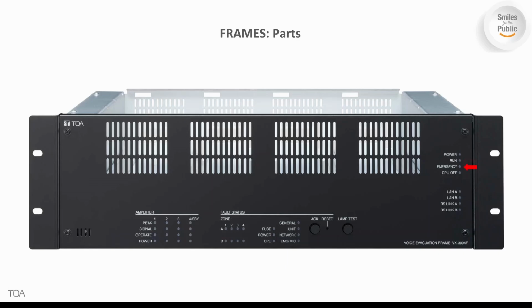The emergency indicator LED provides feedback on whether the system is in emergency mode. It lights red when it's in emergency. The CPU off indicator LED provides notification if the CPU fails. In a CPU off state, this will turn solid red. In a CPU off state, major zoning functions are disabled and only critical functions remain. This will require immediate troubleshooting to address and regain proper function.